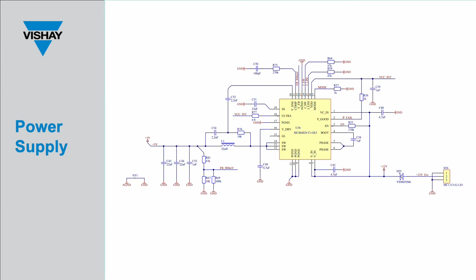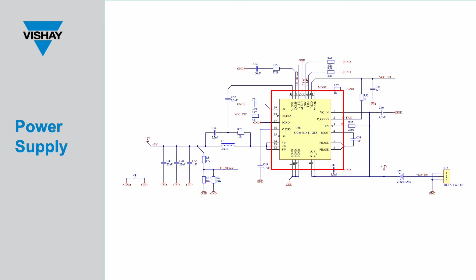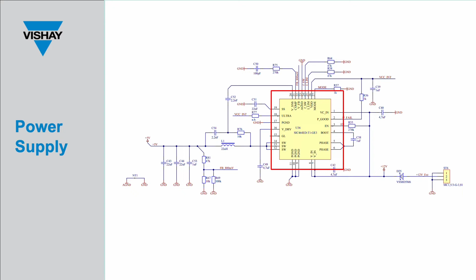In regard to the power supplies required for the operation of the eFuse, it must be connected to an external voltage source between 10 and 16 volts and requires approximately 60 milliamps of current. This external supply is used to provide power for all of the low voltage control circuitry through a 5-volt regulated power supply, which is shown here in the schematic. To minimize the space required, an integrated synchronous buck converter was used, which I'll describe in more detail in the next couple of slides. The external power supply is also used to provide power to the high voltage circuitry, which I described earlier when discussing the isolation barrier.